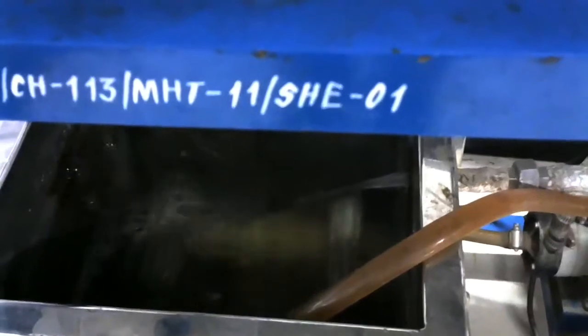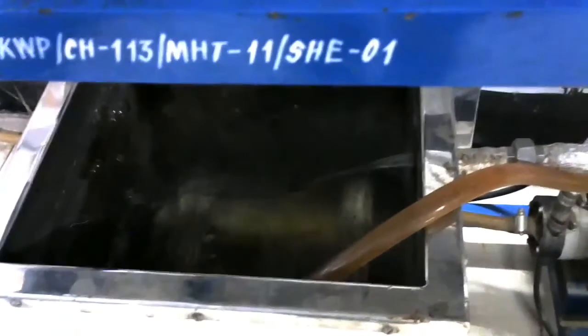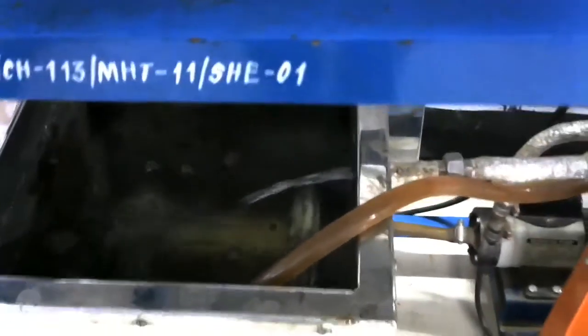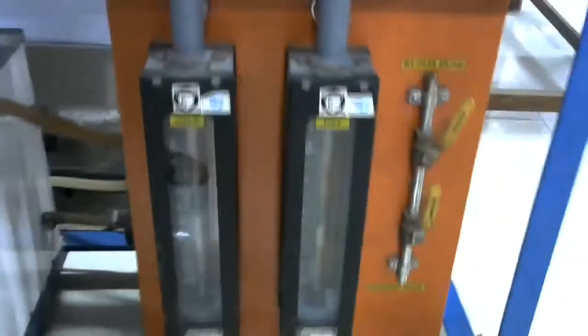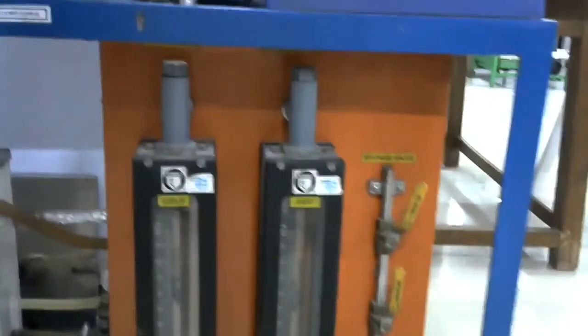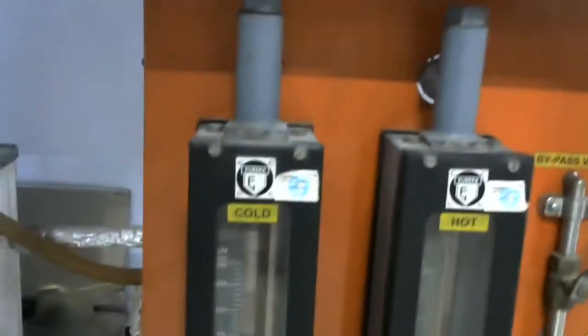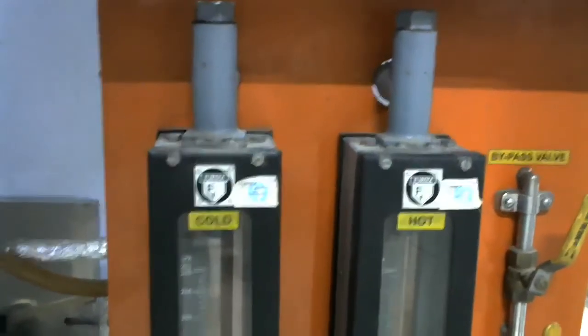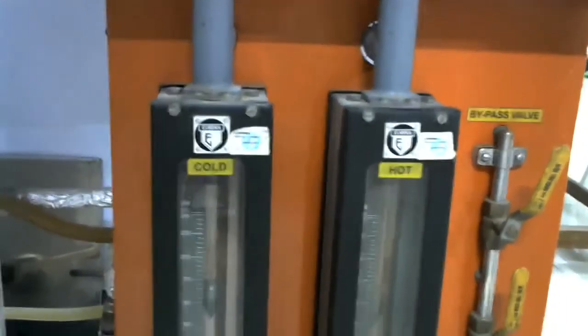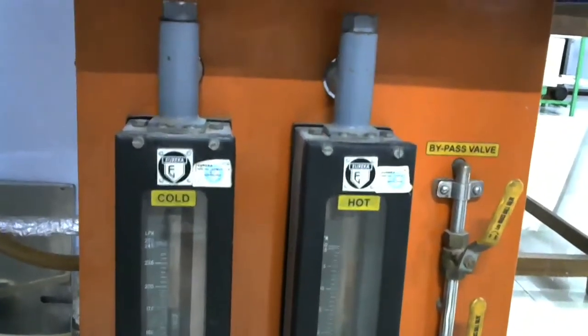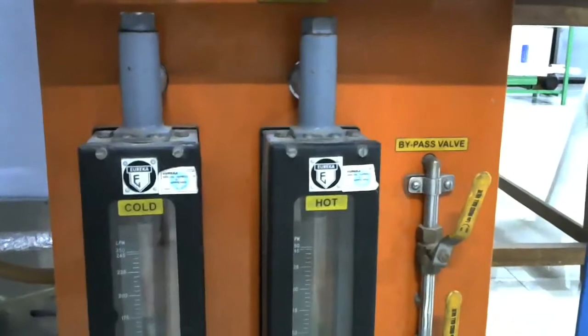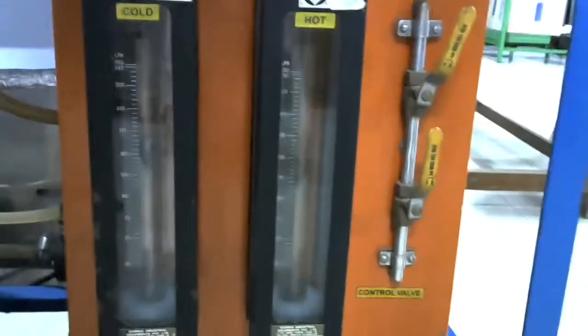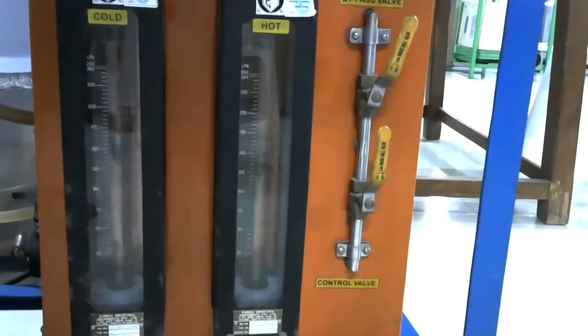So you can observe there are 2 heaters provided in this tank. This is the hot fluid flow to the shell and tube heat exchanger, and another tube is to insert the water in this water tank. You can also observe these rotameters. These rotameters are clearly marked for cold and hot fluid. One rotameter is to measure the flow rate of the cold fluid, and another is to measure the flow rate of the hot fluid. It is in LPH, that is, liters per hour.